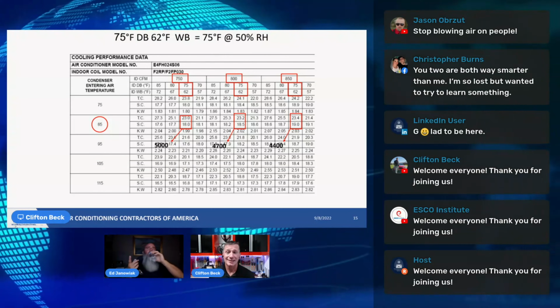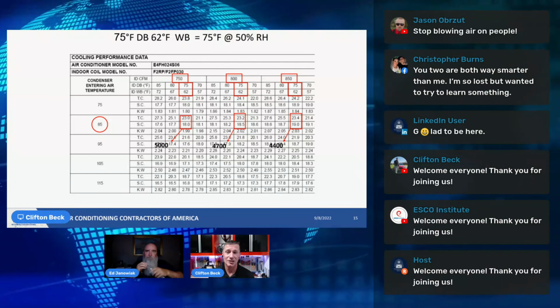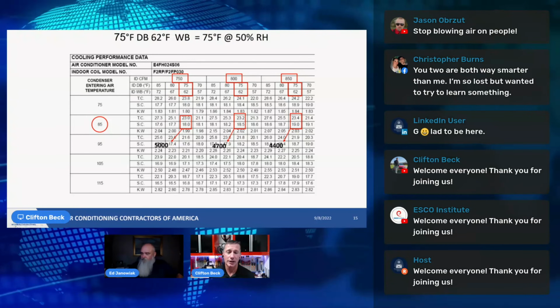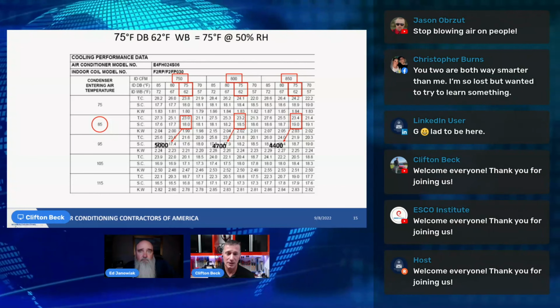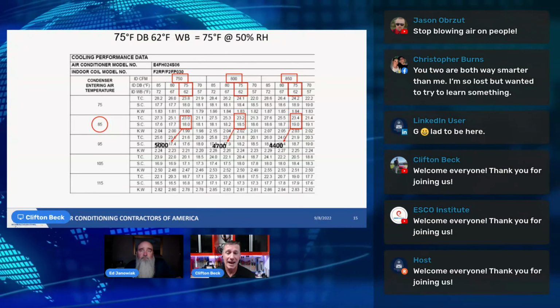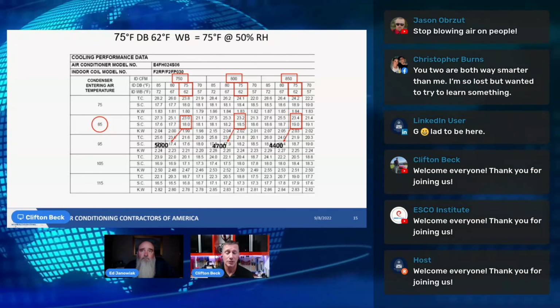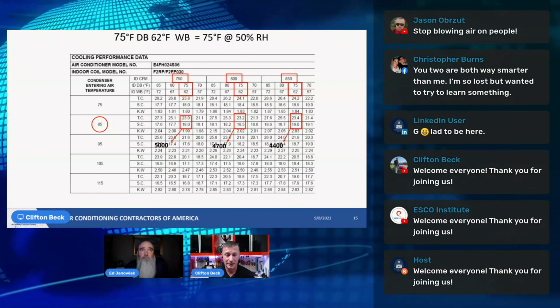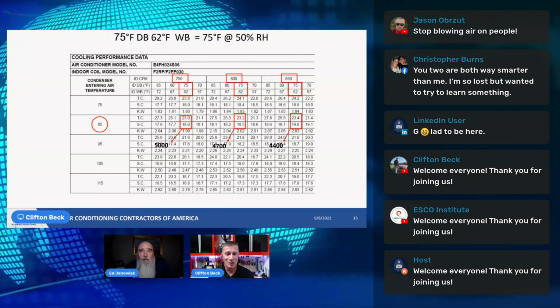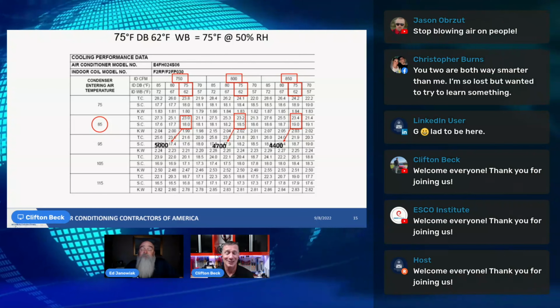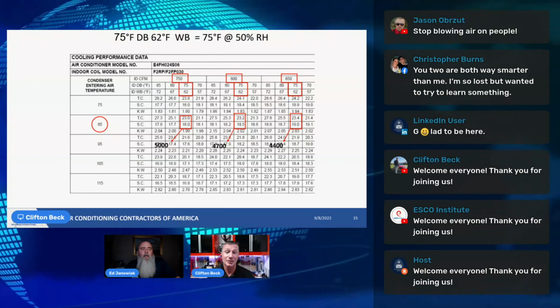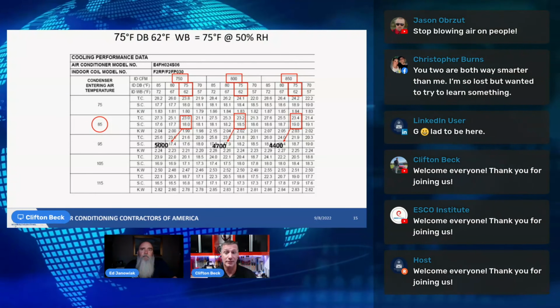Yeah, we're actually going to do a class later in the season where we talk about doing gaugeless diagnostics, because I think it's very critical. If you understand temperatures and humidities, you can determine exactly what your system is doing and be able to calculate capacity of that system. So we might have to come back and regroup on that one again, because that is some really, really good topics to dive into. We'll get into the temperature differentials and wet bulbs of air.